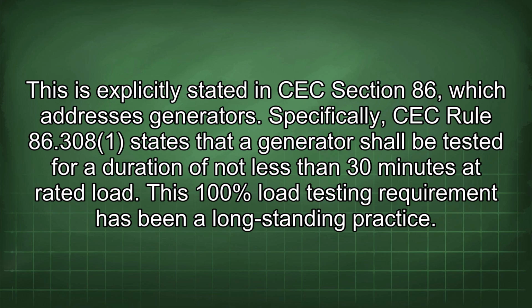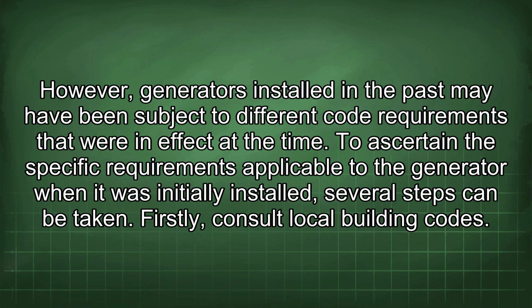Specifically, CEC Rule 86.308 states that a generator shall be tested for a duration of not less than 30 minutes at rated load. This 100% load testing requirement has been a long-standing practice. However, generators installed in the past may have been subject to different code requirements that were in effect at the time. To ascertain the specific requirements applicable to the generator when it was initially installed, several steps can be taken.